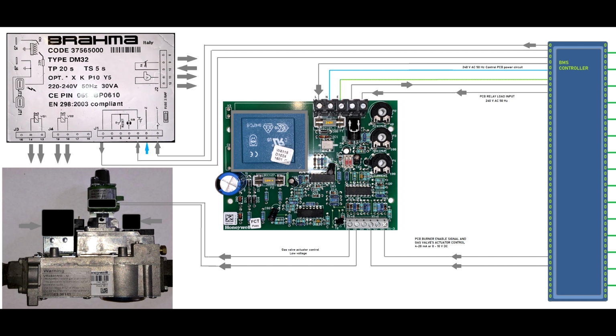The engineer chose instead to return the power into this building management control because in this way, if you monitor remotely this printed circuit board, you will know if this printed circuit board works. I mean, just imagine you will supply 0 to 10 volts to the bottom on the right hand side, and then the signal will be returned and registered by the BMS, and then you will see on your laptop that the printed circuit board is healthy. Now this is the way the technician chose to wire this system. As I said, I'm not going to spend too much time on the Brahma controller. I think as an engineer you know how the gas valve works, and I just explained how this printed circuit board works.